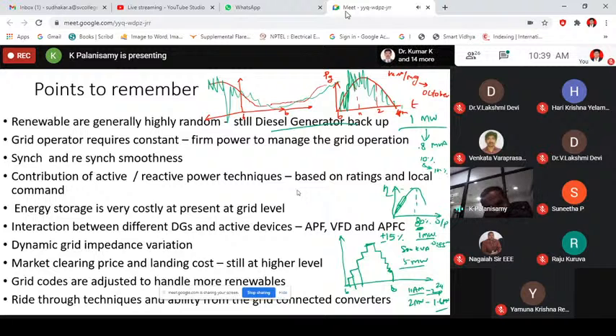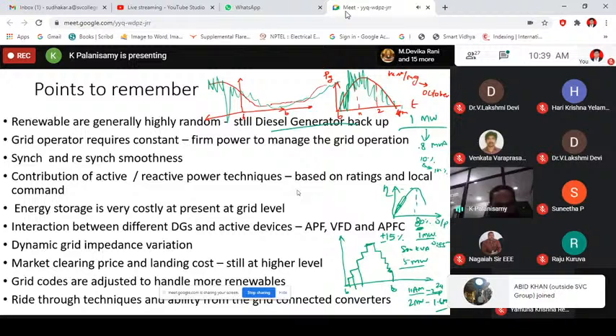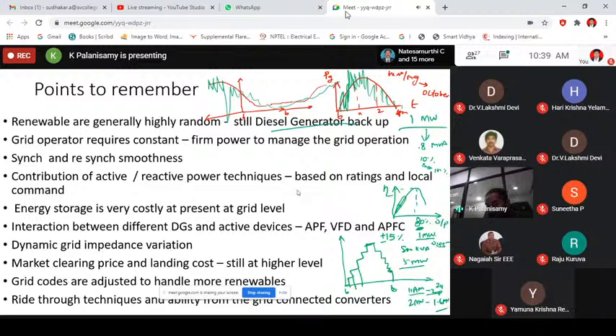If I measure or feel the voltage is greater than the rated, nominal voltage, I will start to absorb reactive power. Of course, I should not, but the recent grid code says you have to support the ride-through for the grid voltage, or voltage support, right? So whenever the voltage goes beyond the rated voltage on the higher side, I have to absorb the reactive power. Sir, you must understand, if you have designed a 1 megawatt solar PV inverter, when it is supplying, let us say, 10% reactive power, accordingly the active power must be reduced, because at any instant or for a longer interval, you cannot overload your inverter.